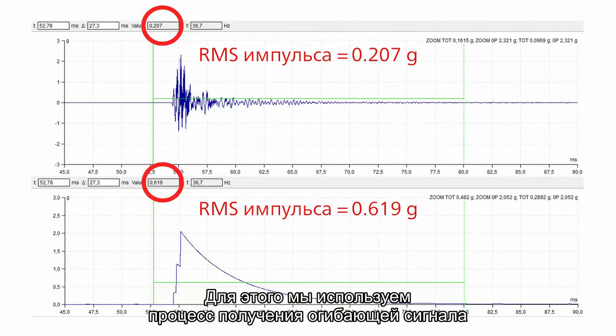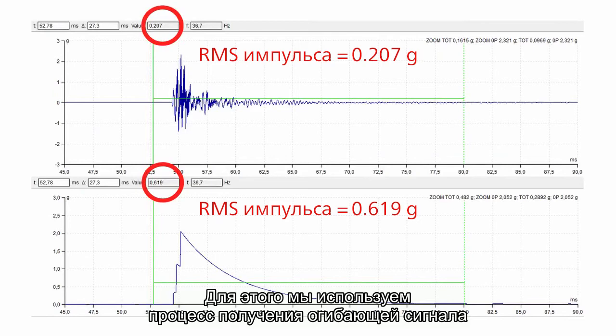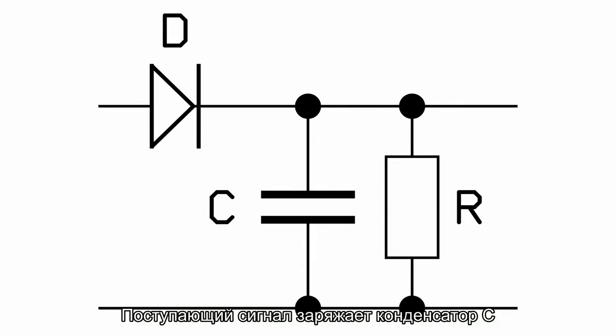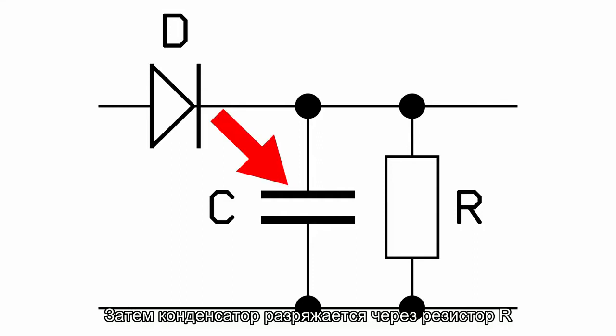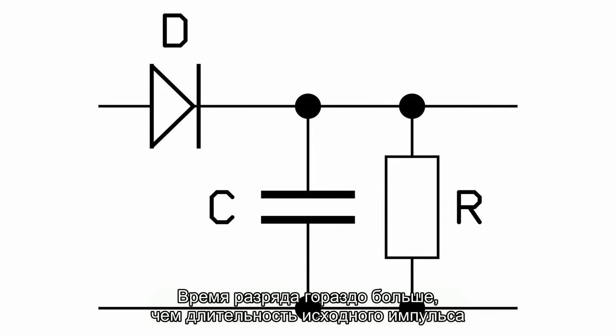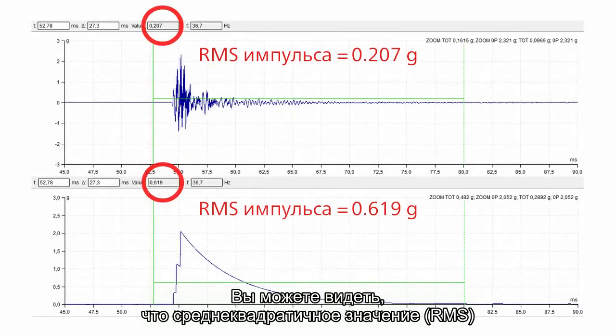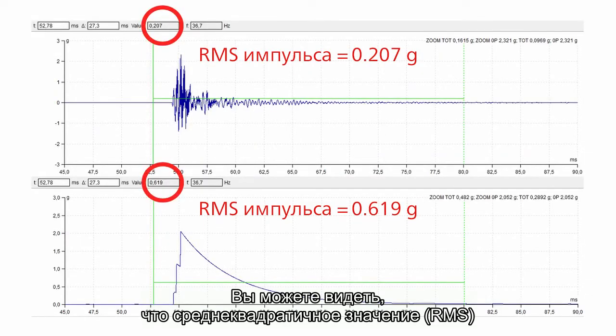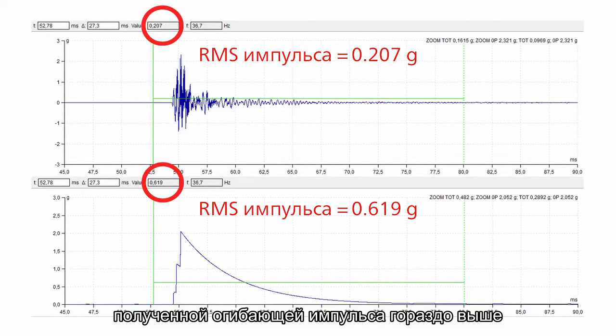We use the enveloping process for that. It adds the energy and changes the shape. You can imagine the enveloping like a simple electrical circuit. The shock comes and charges the capacitor C. Then the capacitor is discharged through the resistor R. This discharging is much longer than the length of original shock. You can see that RMS value of shock after enveloping is much higher. And the shape is changed too.